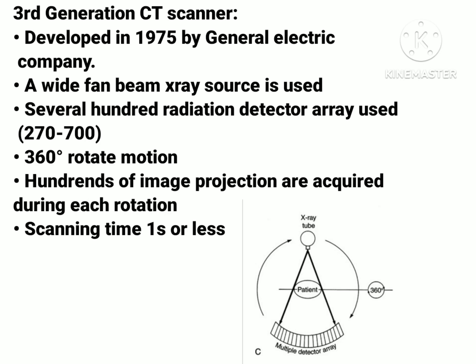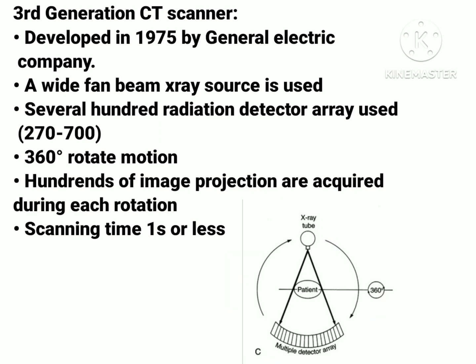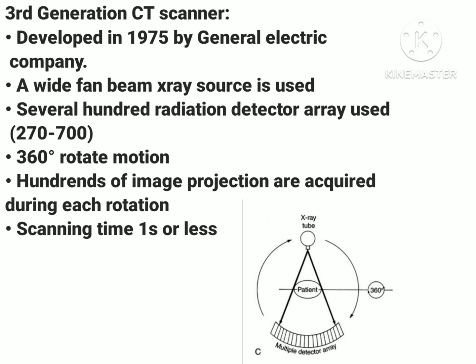Hundreds of radiation detectors were used — approximately 270 to 700. The rotation here was 360 degrees, as compared to the first and second generation CT scanners where the rotation was 180 degrees. In one 360-degree rotation, hundreds of image projections were acquired, and scanning time was one second or less.